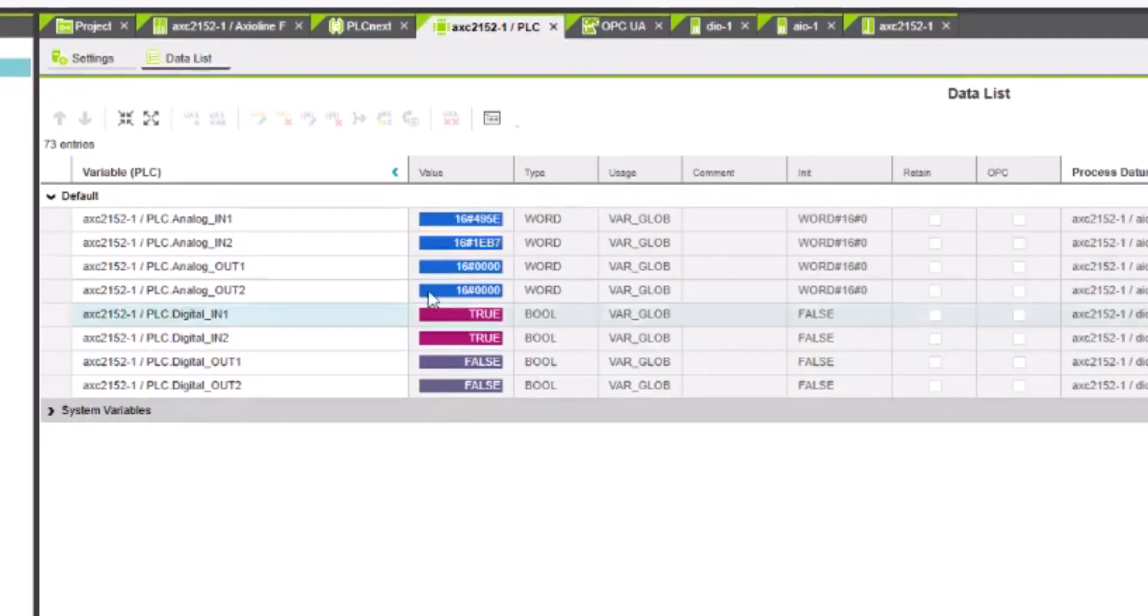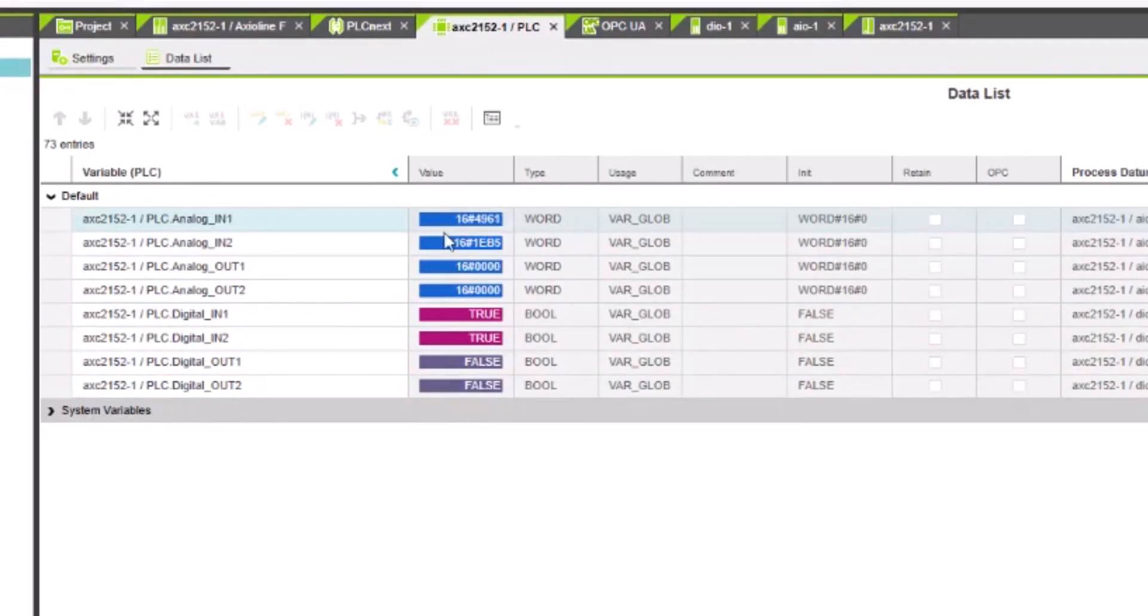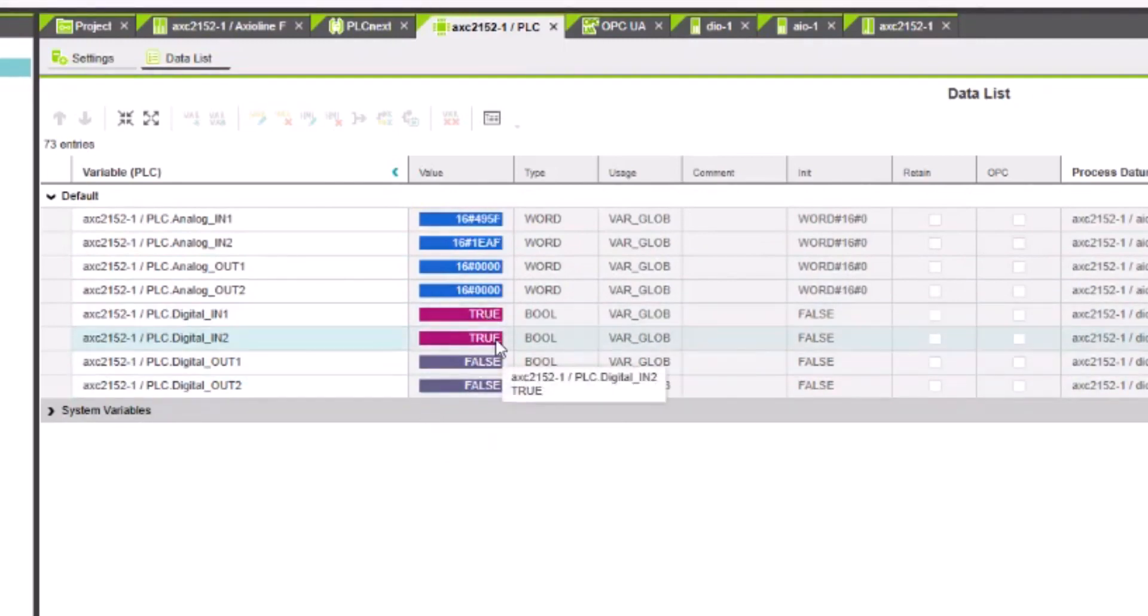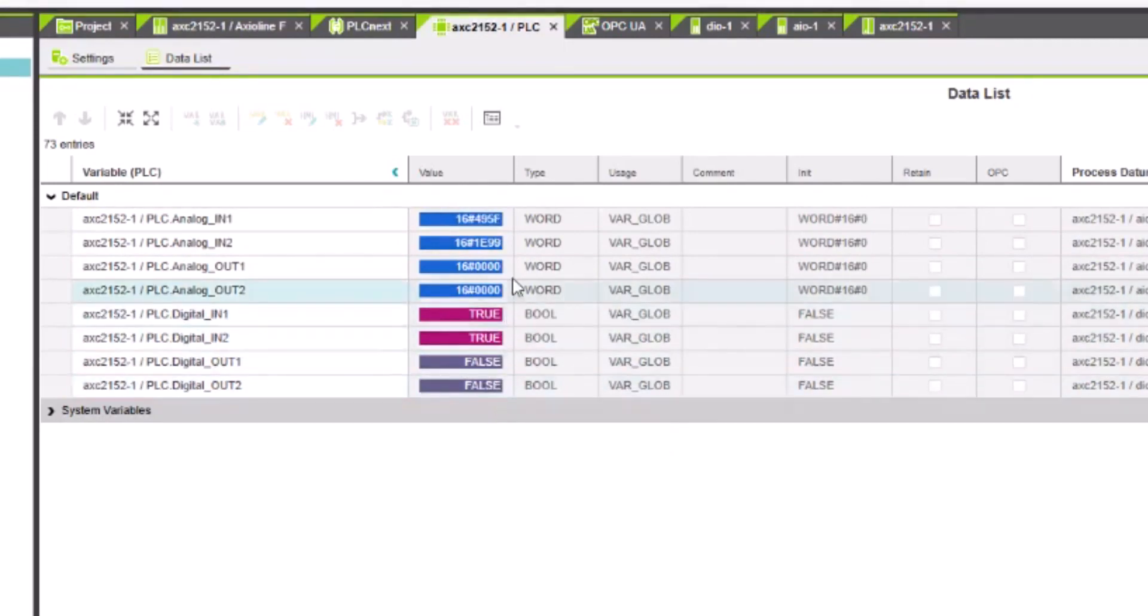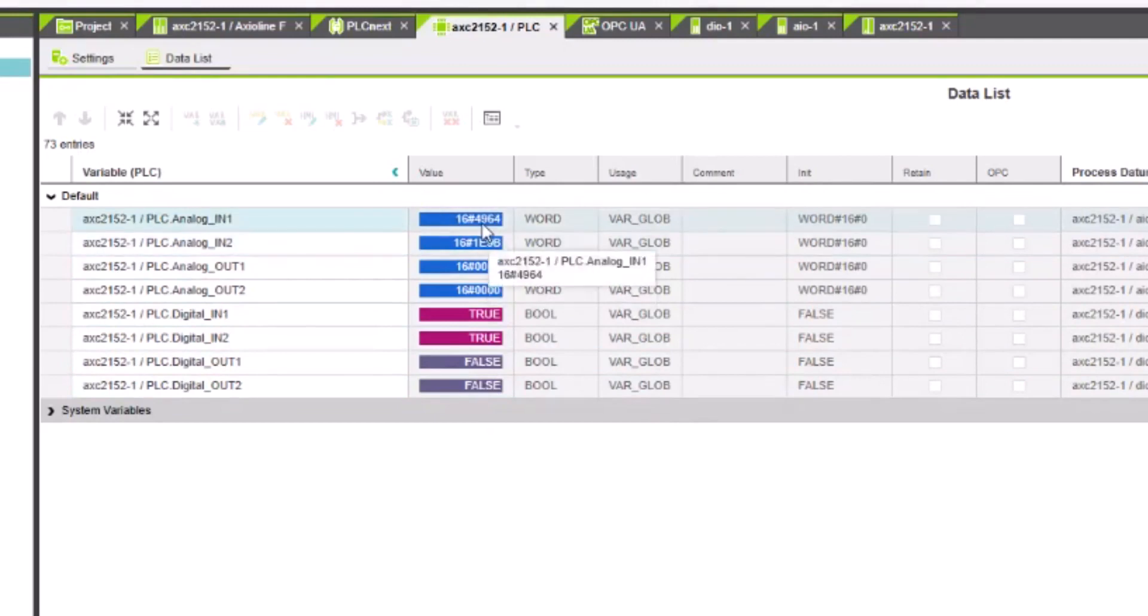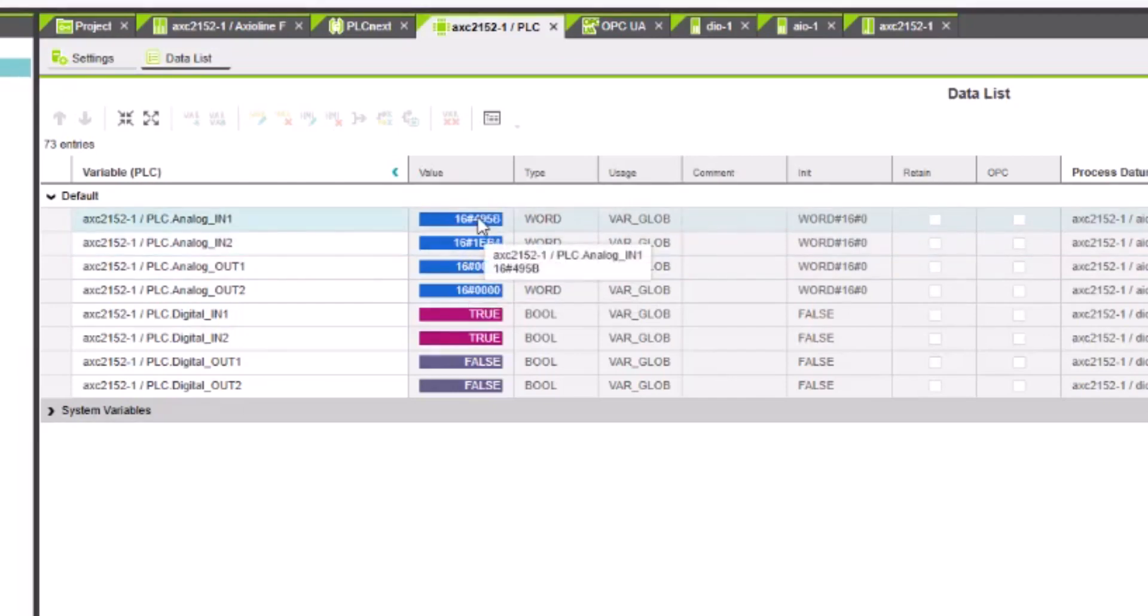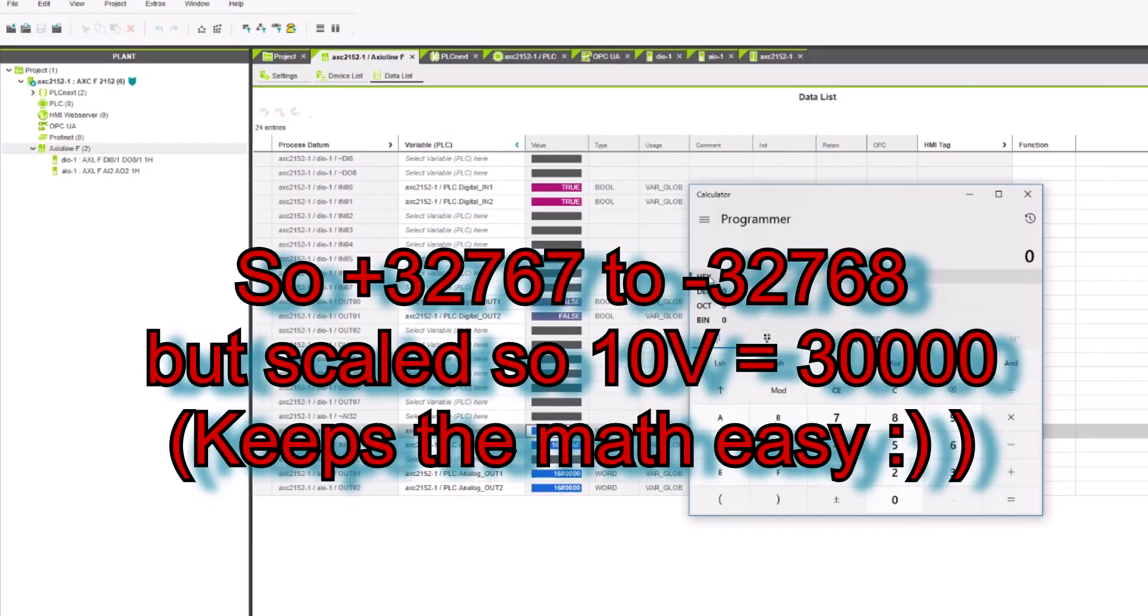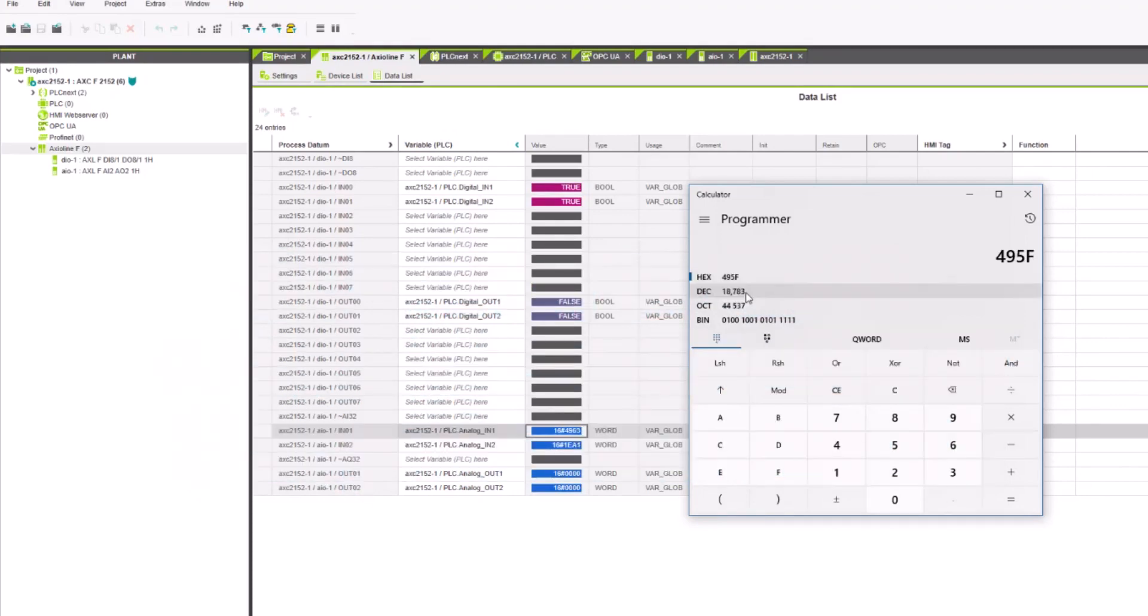Now, according to this, the digital inputs are on, and the digital outputs are off. So if we have a reading for the analog inputs, we have a reading for the analog in two and analog in one. So one of them is connected to the temperature sensor, and one of them is connected to the potentiometer. These are 16-bit converters, digital out and digital in, so signed 16-bit. So let's input the hex value, and you can see here that the decimal value is 18,783. Now, if we go to divide that by 3,000, that should then give us the volts, because that's the conversion. That's what they use for conversion.